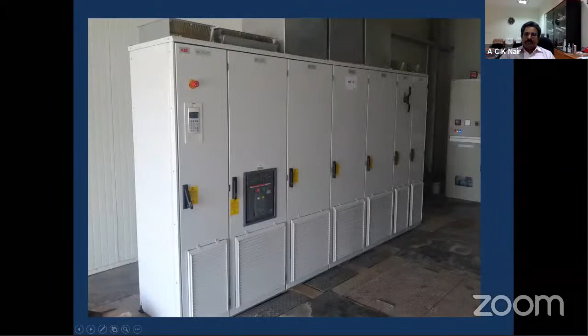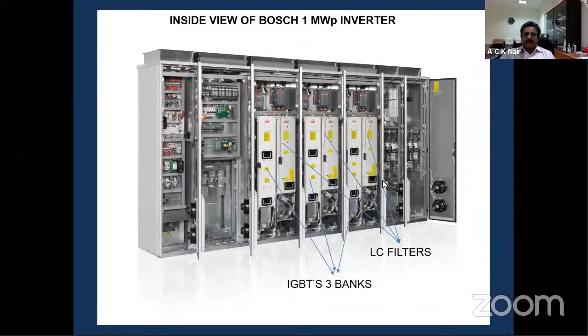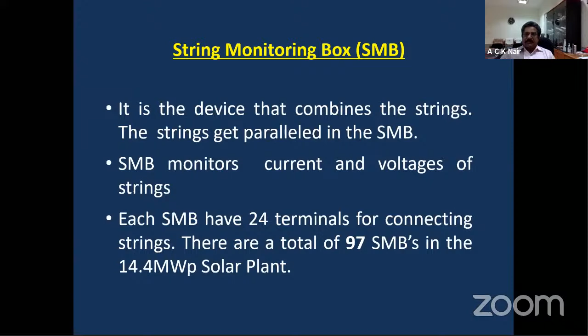These are inverters connected, and this is a panel. This is the string monitoring boxes. I think everybody knows that the string monitoring box is the device that combines the strings. The strings, which are connected in series, are taken in parallel in the SMB. The SMB monitors current and voltage of the string. Each SMB has 24 terminals for connecting the strings. There are a total of 97 SMBs in the 14.4 megawatt solar plant itself. These are these SMBs.